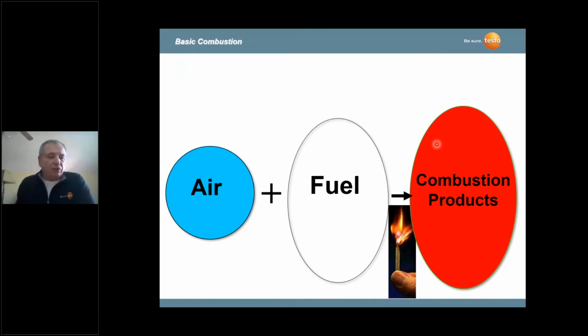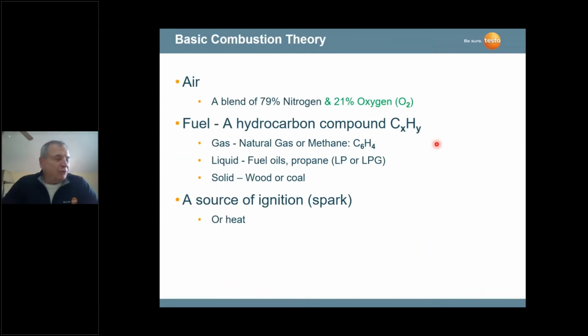Some basics on combustion: air, fuel, combustion products. You need a heat source to create combustion. So we have air and we have fuel. We ignite those two together. We have combustion products creating heat. Heat goes out the stack. Heat is also absorbed in our heat exchanger or boiler tubes so that we can move that heat throughout the building. Air is very critical, obviously, and as you probably all know, air, even in Canada, is 21% oxygen. So if we take a deep breath right now, we're breathing in 21% oxygen. The balance of that is primarily nitrogen.